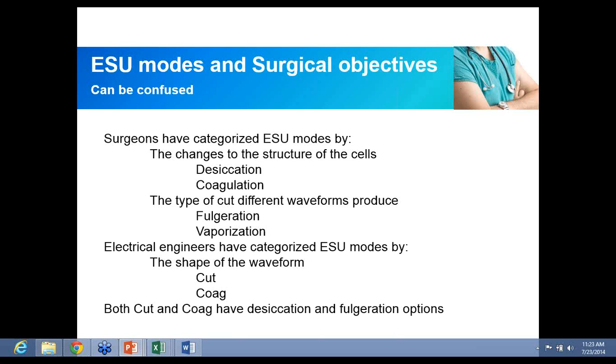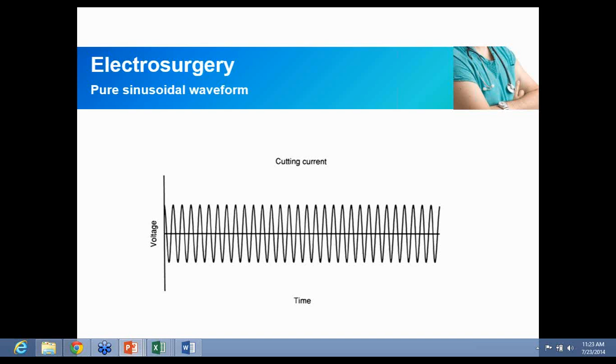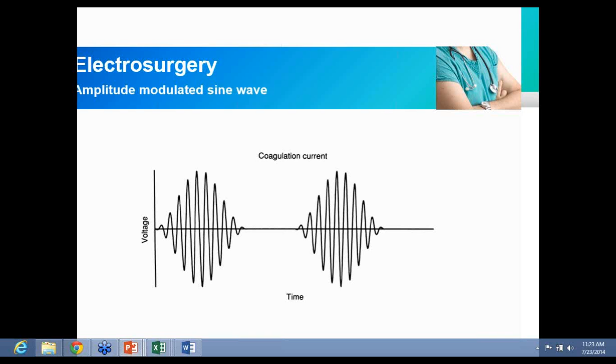But when coag is done, remember, coag has to achieve a higher current density. So the frequency gets higher, and so does the amplitude modulation of that frequency. So the waveform gets narrower and then wider, and as it gets narrower, the amplitude increases. So here's an actual oscilloscope capture of a full duration waveform. Notice that the amplitude of this waveform is uniform in its change. It increases and decreases, okay? And also, if you notice, the frequency is very uniform.